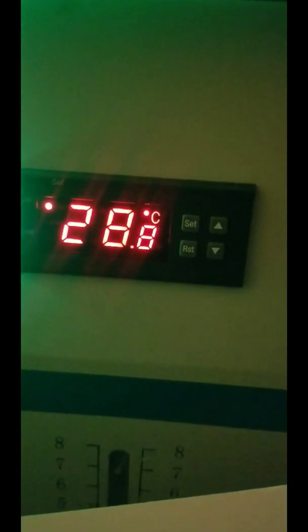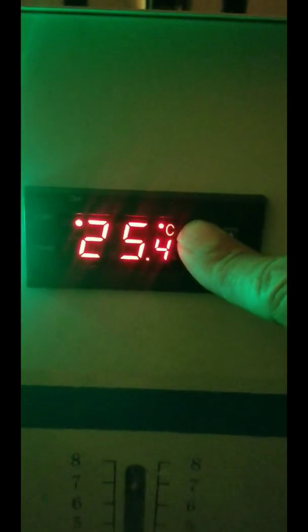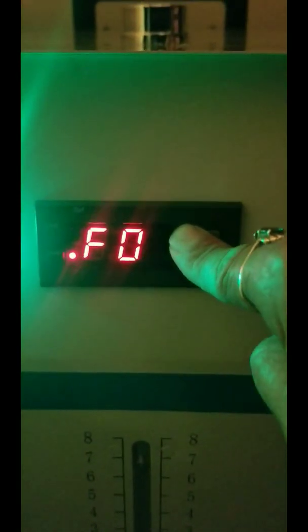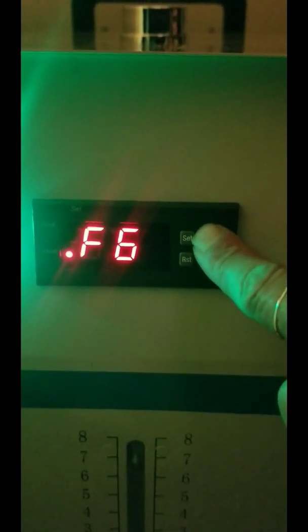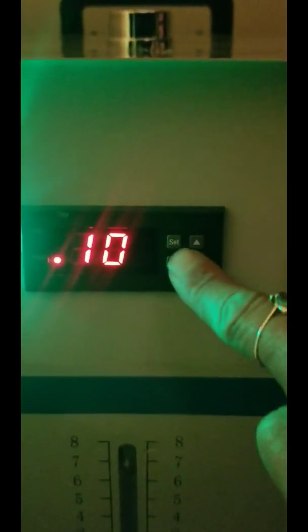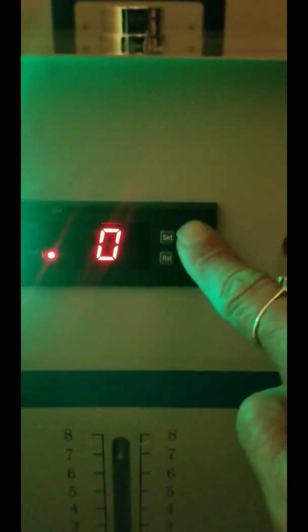F9 is compressor delay, from zero to 99, and it should be set to 60. I think this actually means 60 seconds. Because when you go in it just goes 1, 2, 3, 4, 5, 6, 7 — up to 10. So I think this is actually measured in minutes. We'll just leave it at one minute.